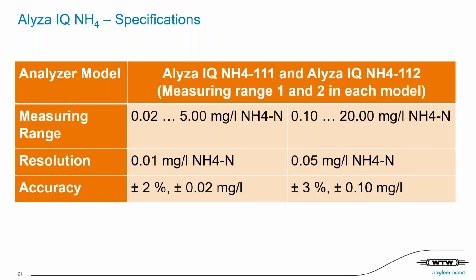So now let's review some of the specifications. Ammonium Alyza IQ provides two different measurement ranges in one model. Measurement range 1 is from 0.02 up to 5 milligrams per liter with a resolution of 0.01 milligrams per liter and an accuracy of plus minus 2%. The measurement range 2 is 0.10 up to 20 milligrams per liter with a resolution of 0.05 milligrams per liter and an accuracy of plus minus 3%. With this high accuracy at very low concentrations, Alyza IQ ammonium is perfectly suited for different monitoring tasks.